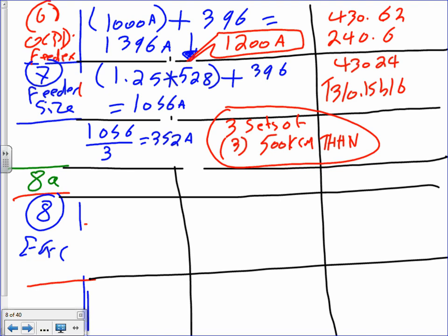Okay, the last thing I have, I'm going to get rid of this one so it doesn't confuse you, is number 8. You guys remember what number 8 says? This is for M number 1, motor number 1. This is M number 2. Number 8, anybody look at number 8? What was number 8? Equipment grounding conductor. I need to pull an equipment grounding conductor with motors inside the flex, guys, always inside the flex. Okay, equipment grounding conductor, guys, piece of cake.